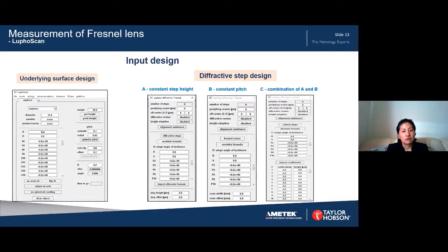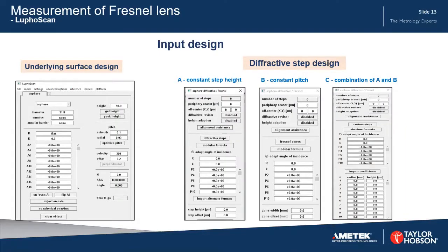For Fresnel lens measurement, before starting you need to input the design. The design is separated into two different parts: one is the underlying surface design, which you can type into the main interface, and the other is the diffractive step design. The software covers all three different types of Fresnel lens designs: type A (constant step height), type B (constant pitch), and a mix of type A and B.